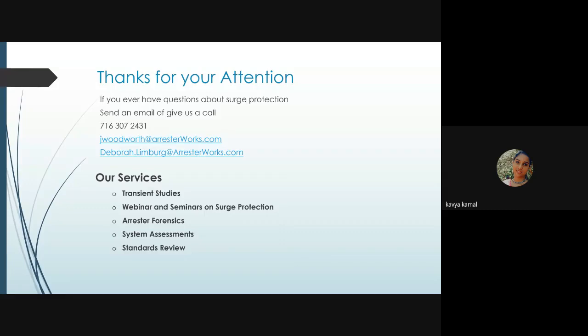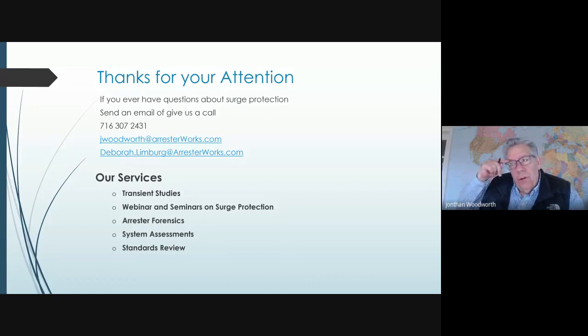Is SPD still necessary even if we have good grounding? Well, it depends on what you're trying to protect and what your goals are. If you have good grounding and you are in a very, very low lightning area, don't put the SPD up. There's no real need to. If you're in a high lightning area, grounding will not help you. You need the surge protector. And if you're referring to an SPD as a low voltage device, which is typically the term for low voltage devices, the cost of an SPD is so low compared to the cost of replacing a piece of equipment. It's very low cost insurance.